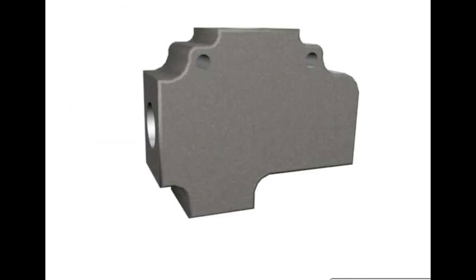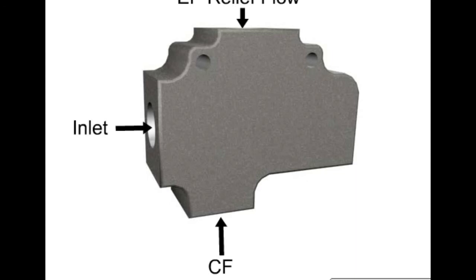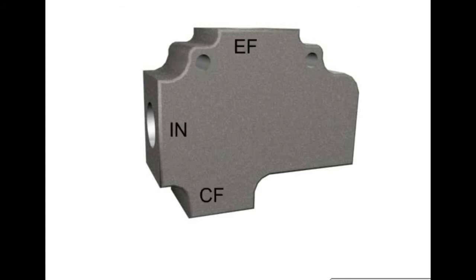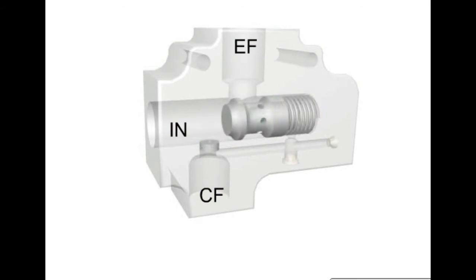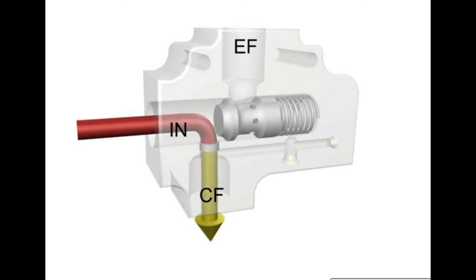This is a pressure compensated bypass flow control. Bypass flow controls are often used for priority flow dividing applications. The primary components are the housing, the main spool with a metering orifice, the spool biasing spring, and a relief valve. The metering orifice controls the amount of flow to the priority circuit. The biasing spring holds the spool to the left, blocking the flow path to the excess flow port.